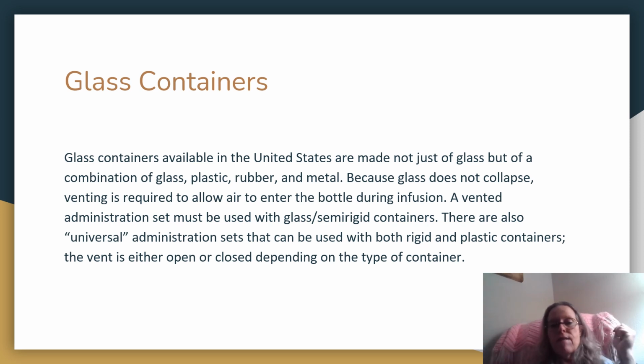So this is why we use a vented administration set. This allows for the air to come in and out. They're also called a universal administration set because it can be used with anything. And just because it has a vent on it doesn't mean it can't be used with a plastic type of container. So again, it just depends on the container. You have to have a vented infusion device and tubing with a glass bottle. However, with a plastic bottle or plastic container, you can have either or. So just make sure you know that.